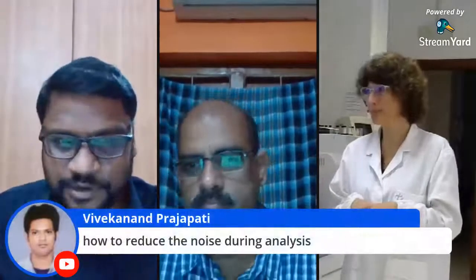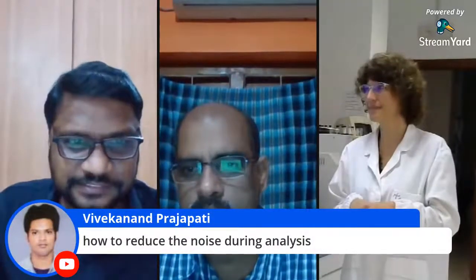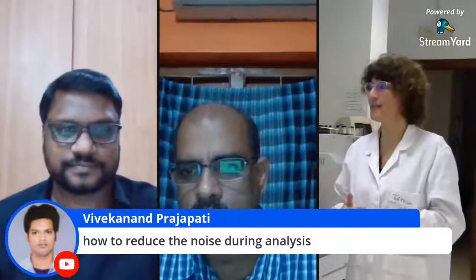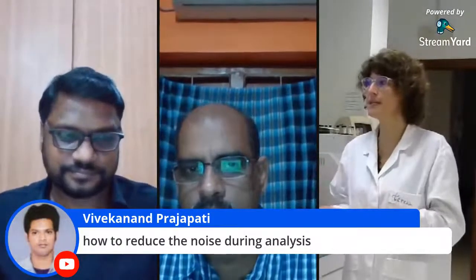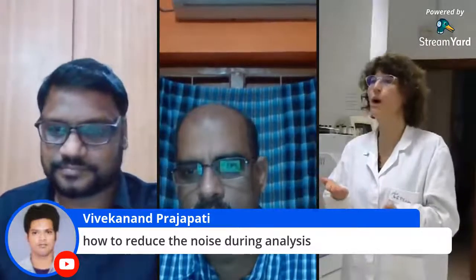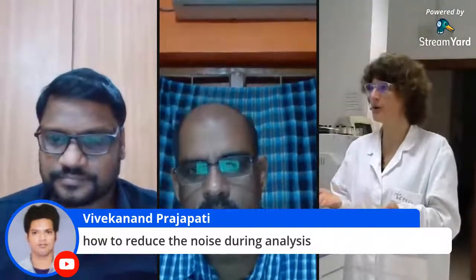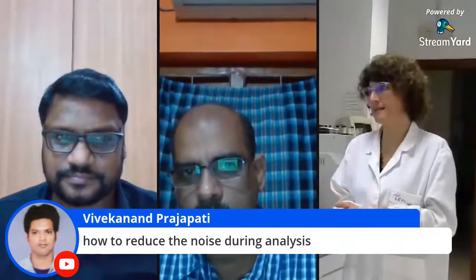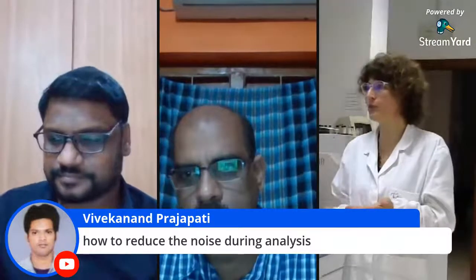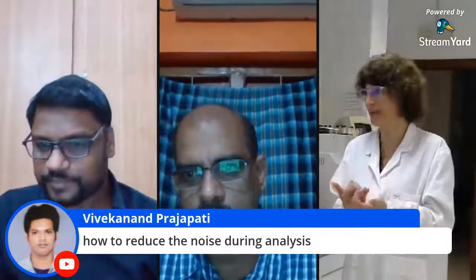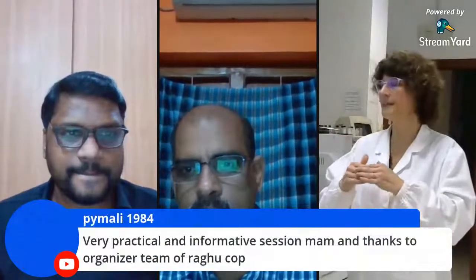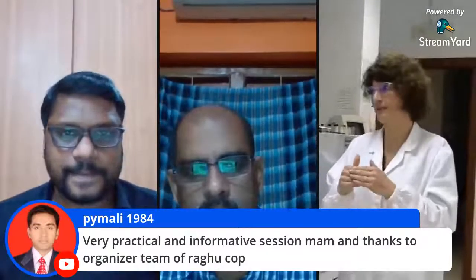Sir, one question from Vivekanand Prajapati. Yes, one way to reduce the noise during analysis, for example, if you are using IC, ion chromatography, can be the use of a suppressor. The suppressor would reduce the conductivity, the high conductive environment of the eluent, by combining H plus and OH minus, for example, and in this way the conductivity would really be decreased because it's water that you now have, and water is not conductive actually.